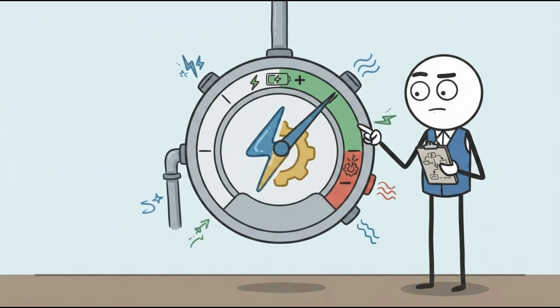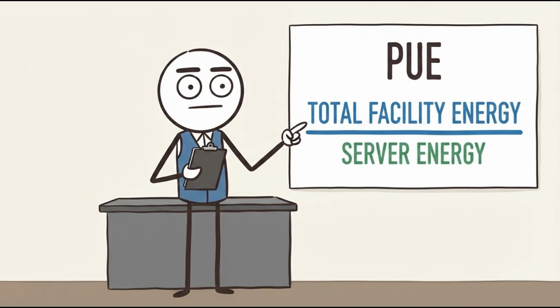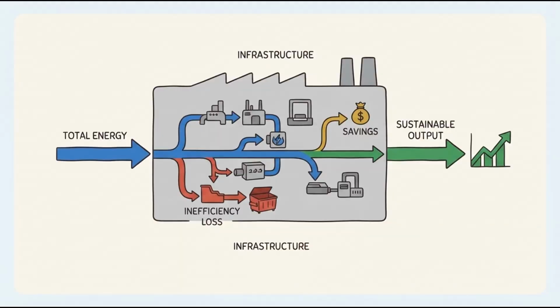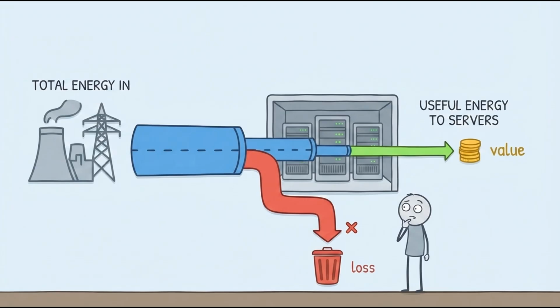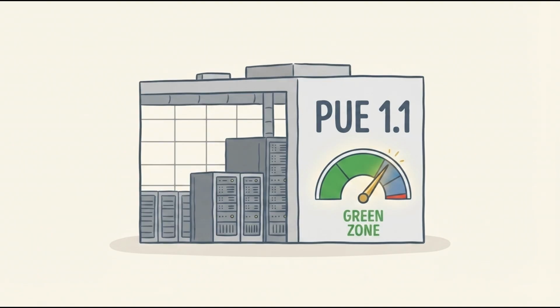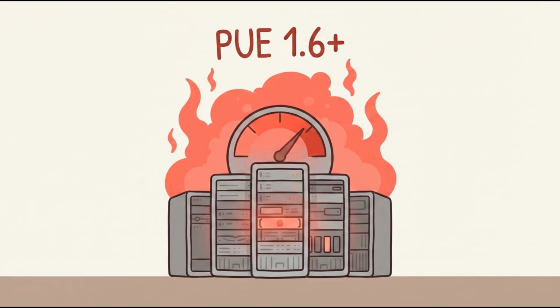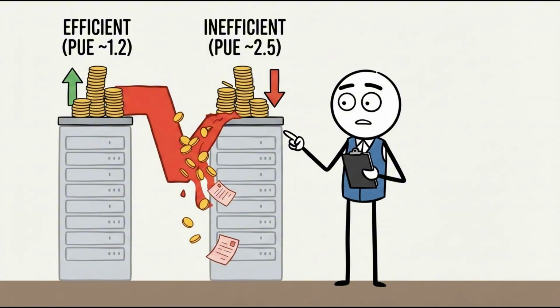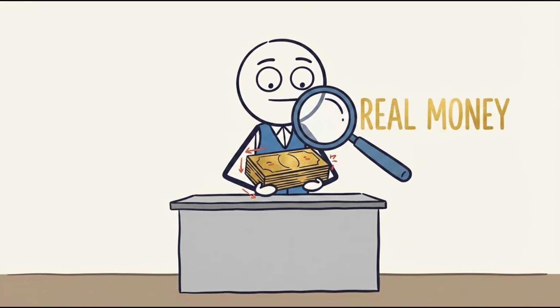The industry measures this efficiency obsession through a single metric called power usage effectiveness, or PUE, the ratio of total facility energy consumed against the energy actually reaching the servers doing useful work. A best-in-class hyperscale facility runs a PUE around 1.1, while an older, inefficient building can run 1.6 or higher. And that gap is not a rounding error, it is real money.